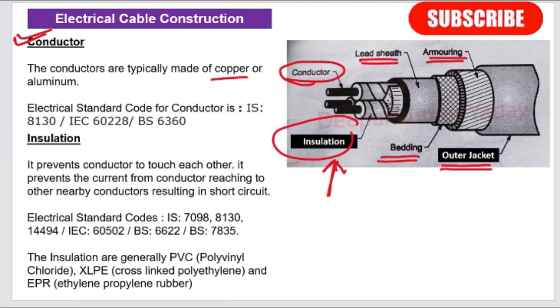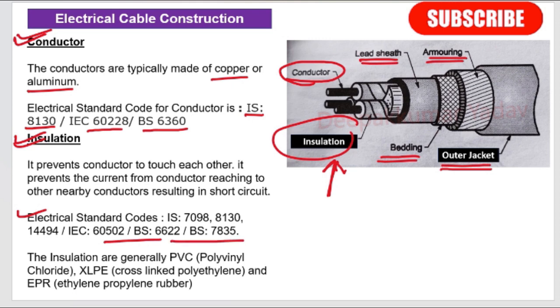Conductors are generally made of copper or aluminum. Electrical standard codes for the conductor are IS 8130, IEC 60228, and BS 6360. The insulation prevents conductors from touching each other, preventing current from reaching nearby conductors and causing a short circuit. Electrical standard codes for insulation are IS 7098, IS 8130, IS 14494, IEC 60502, BS 6622, and BS 7835.